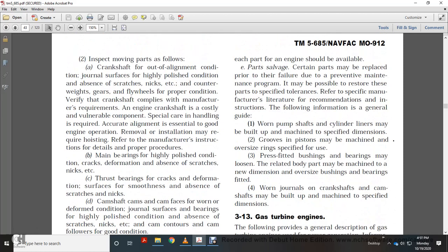Certain repair parts should be available immediately. Parts that should be renewed with each overhaul include gaskets, rubber sleeves, and seals. Parts with predictable service life requiring periodic replacement include fuel injector pumps and governor valves, which should be renewed within one year. Parts with long service life include cylinder heads, cylinder liners, pistons, connecting rods, gears, chain drive parts, and oil pressure pumps. Worn pump shafts and cylinder liners may be machined to specified oversized dimension groups. Pistons may be machined to oversize with appropriate rings. Bearings may be rebushed. Crankshafts and camshafts may be built up and machined to specified dimensions.